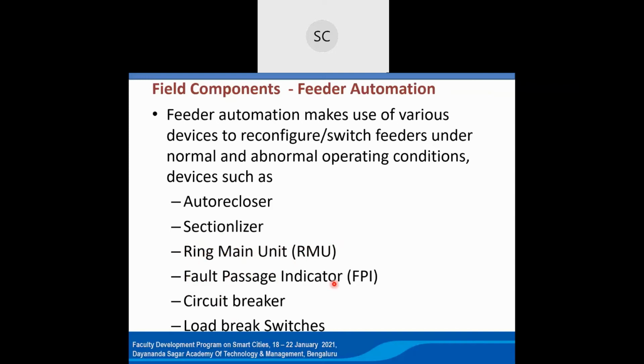Another item is the fault passage indicator. This fault passage indicator is nothing but a small over current relay and an earth leakage relay, both built in as functions, installed on the 11 kV overhead live lines. When a fault happens, it will trip, and the associated indication lamp will flash at a quarter rate, so that when the crew comes from the utility, they can identify, trace and rectify the fault. The fault passage indicator also indicates at the control center exactly where the fault happened. When the lineman comes to a densely populated area, he can quickly identify the fault location by seeing the indicator. Circuit breakers and load break switches, as you have seen in the substation, are used in a similar way in feeder automation.